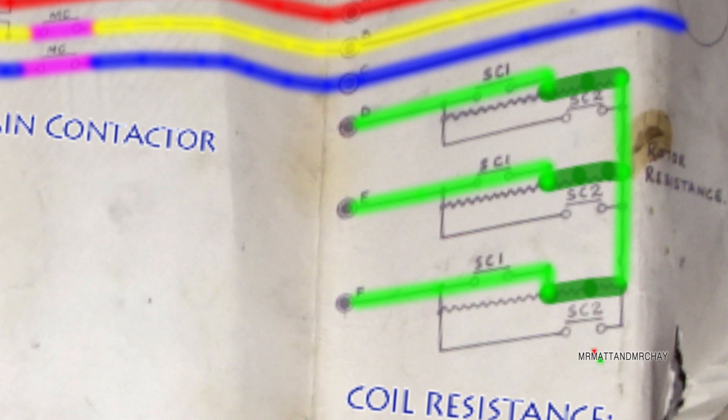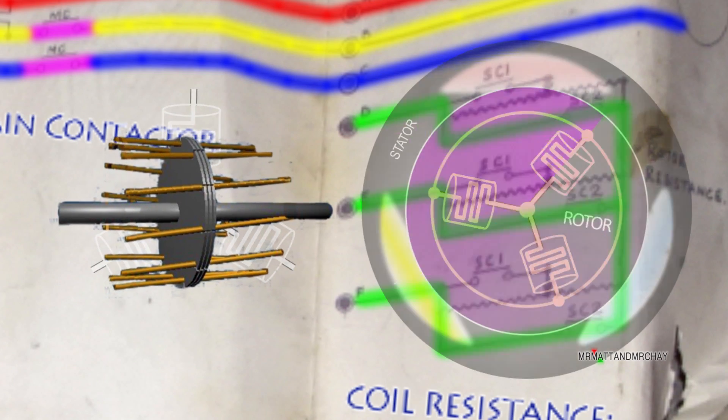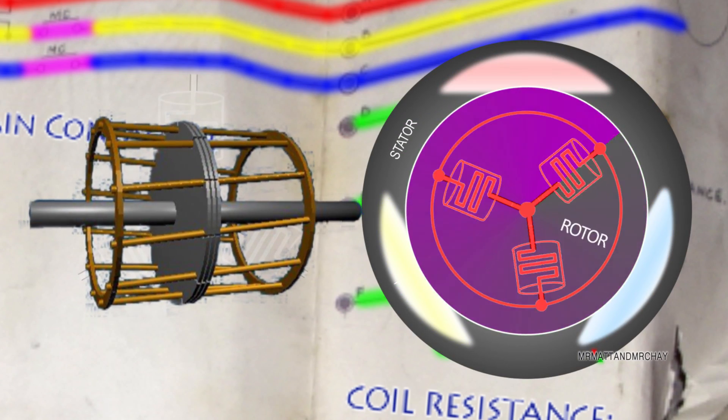One and a half seconds later, SC2 activates, which causes all three resistors to be shorted out. With no resistance at all in the circuit, terminals D, E and F are now connected together to create a conventional caged motor, which is best for normal running.